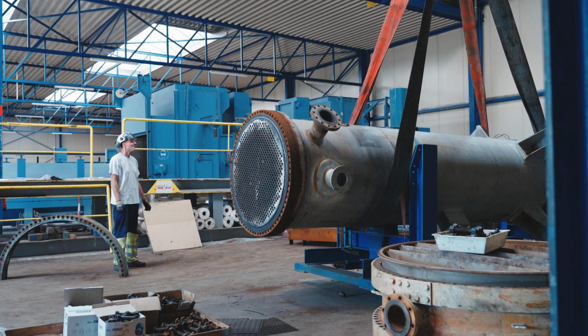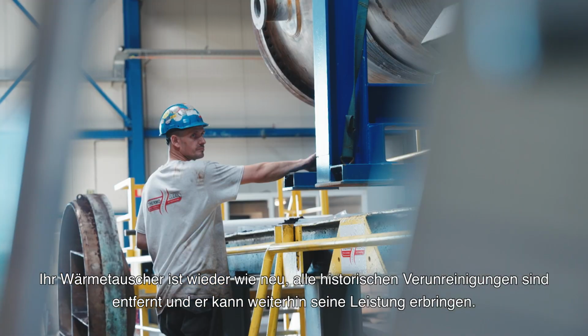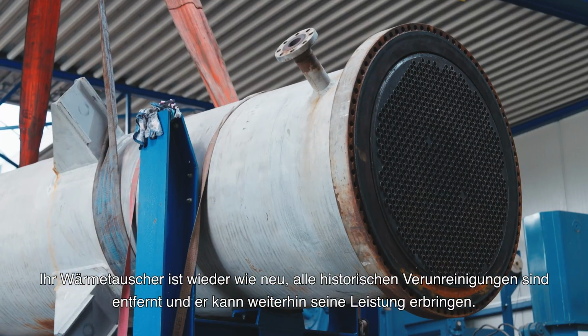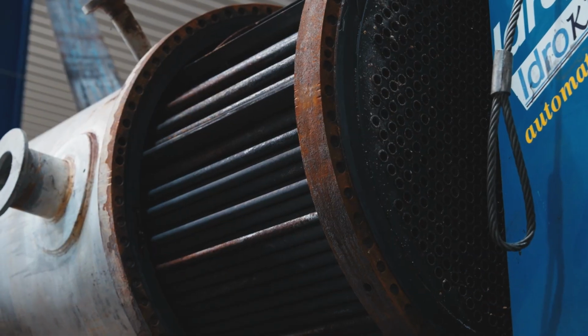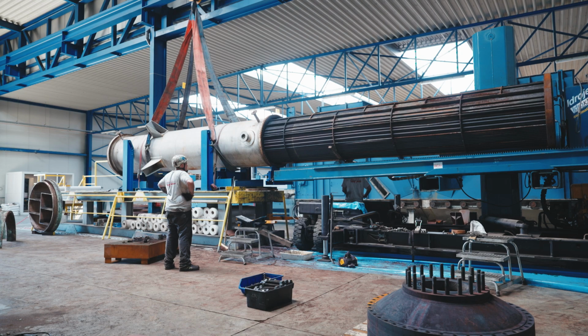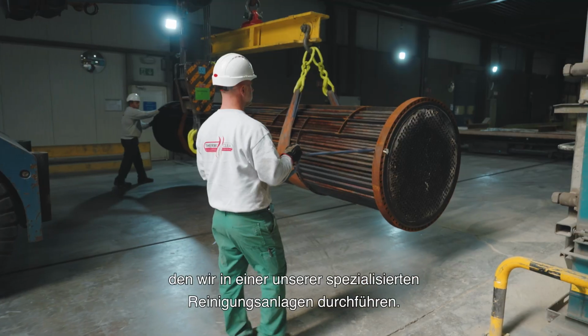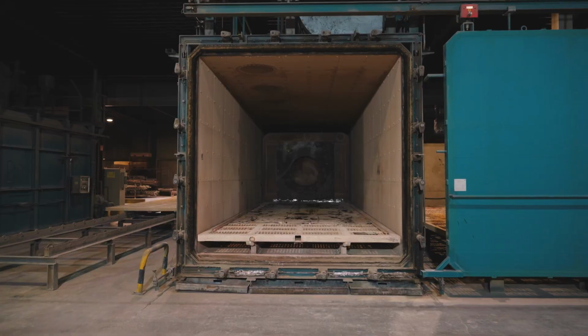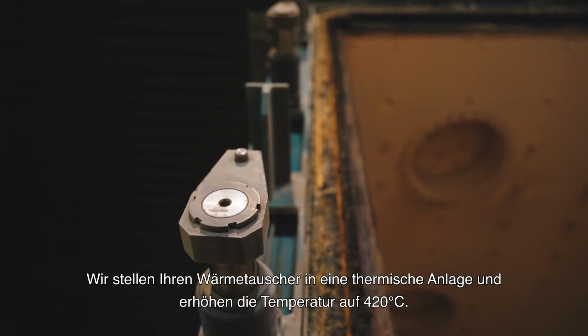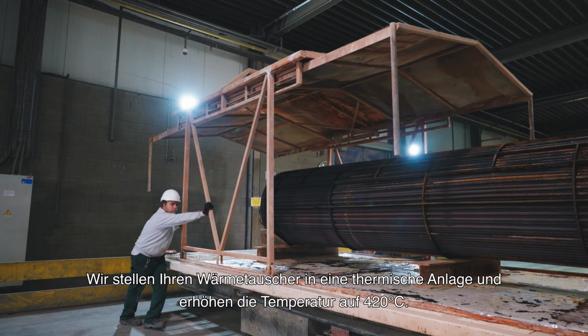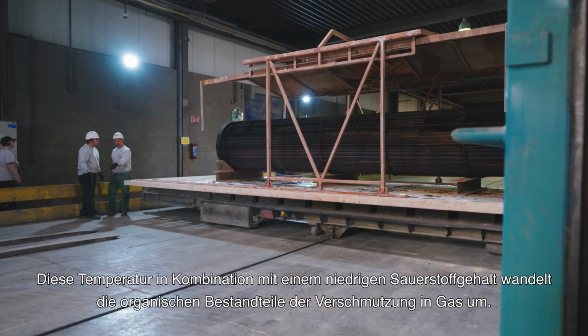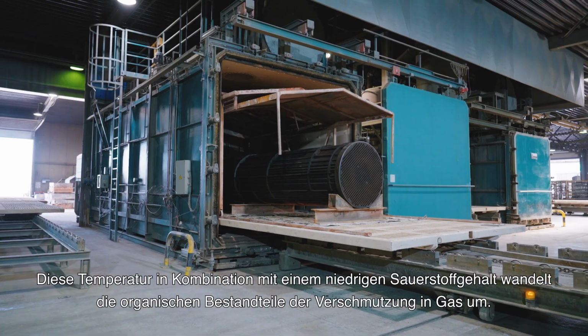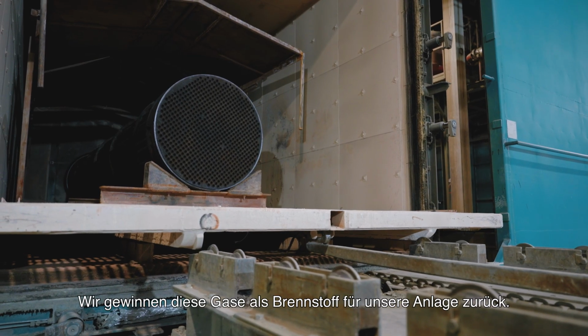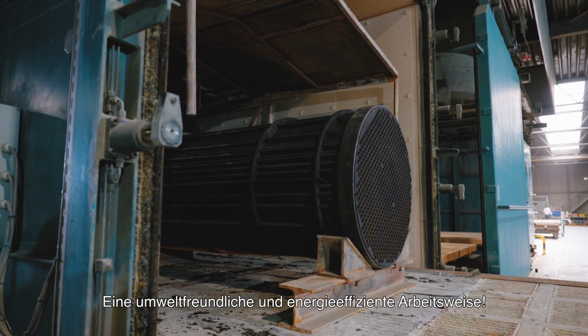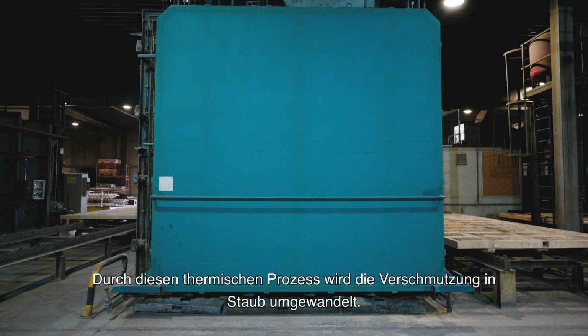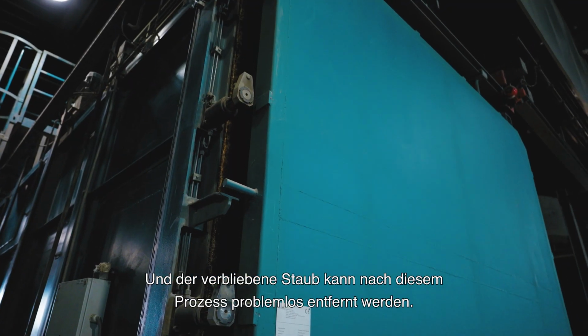The proper solution: thermal cleaning. Your heat exchanger will be as good as new, without any historical contamination, but with a continued efficiency and optimal TCO, year after year after year. Thermal cleaning is a controlled purification process performed in one of our specialized cleaning facilities. We place your heat exchanger in an oven, after which temperatures are increased up to 420 degrees C in a controlled way. Those high temperatures, combined with a low oxygen level, convert the organic components of the contamination into gas. We recuperate those gases to be used as fuel for our oven, an environmentally friendly and cost-efficient process. This thermal process converts fouling to dust, which we rinse out afterwards.